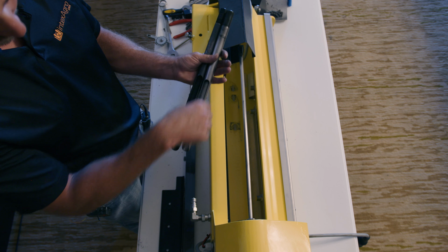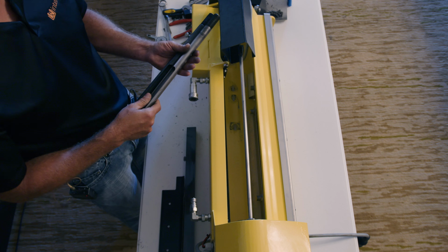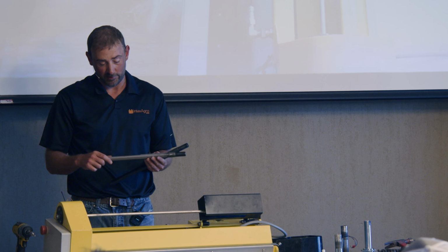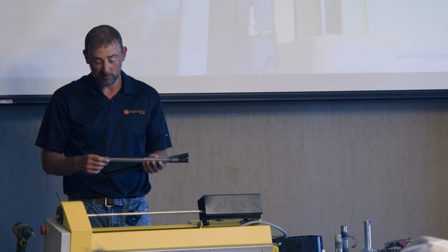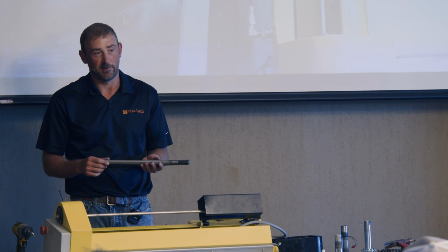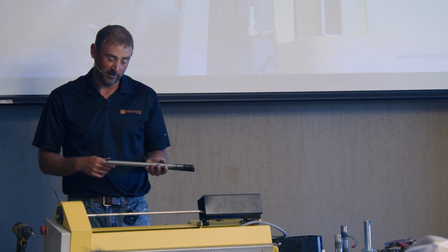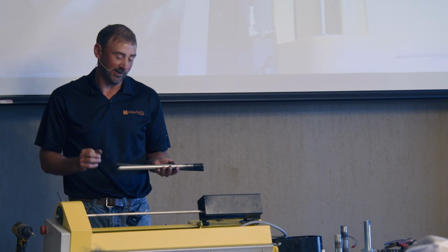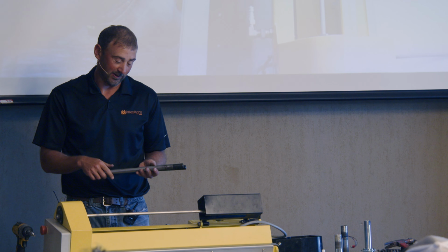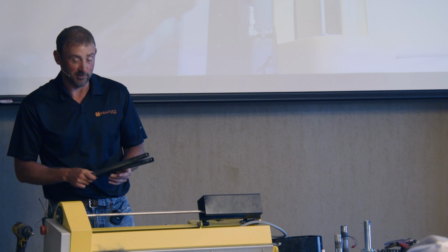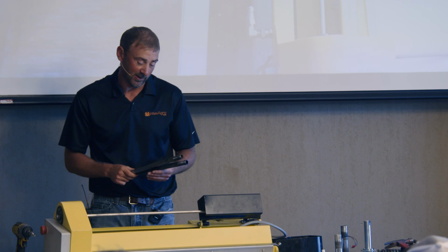Should be tight with an ejector tip, tight the whole way. If you start seeing play, you could put a tip in the end, hold it up. You shouldn't see daylight through it. If you do, then your probe needs to be replaced. And then, sand, dirt, no moisture, you can use old probes for a long time. If you get in really mucky situations, you need it to clean out perfectly every time. Otherwise, they'll start gumming up, so that's when you want a new probe and new tip.